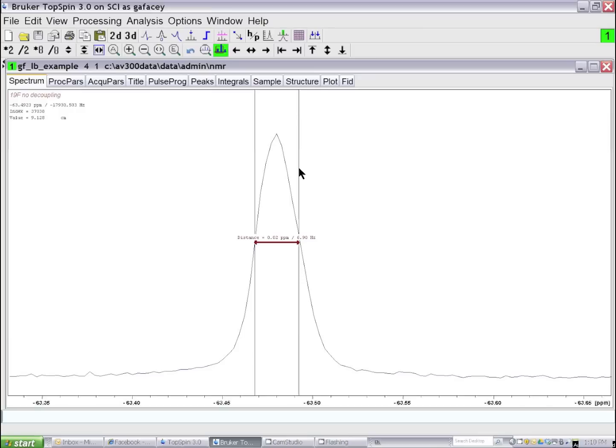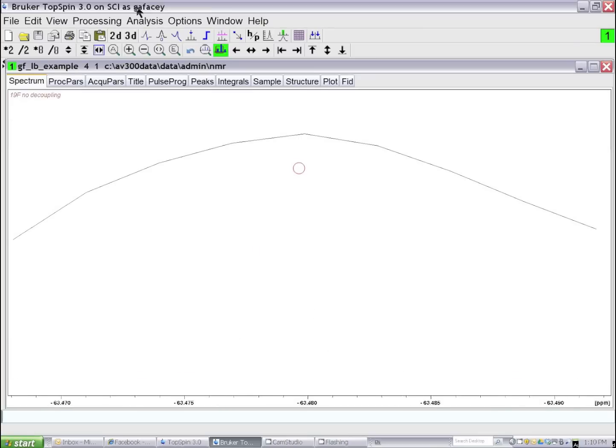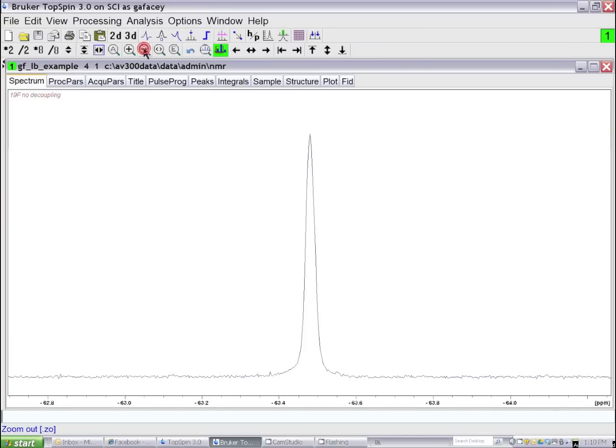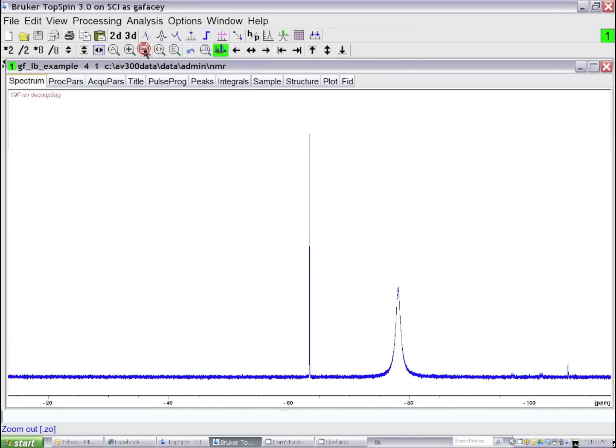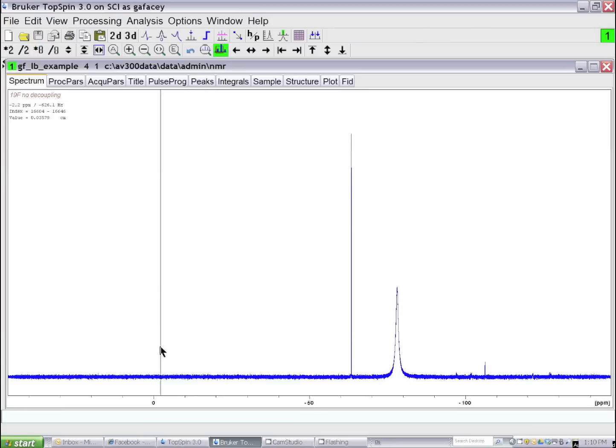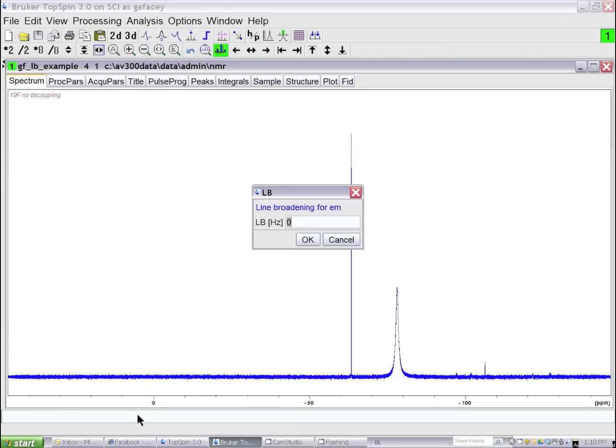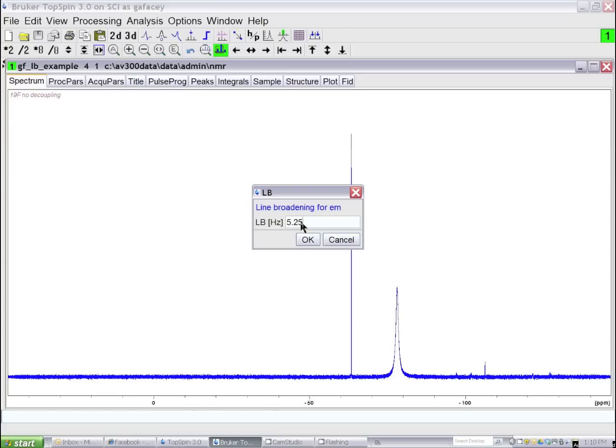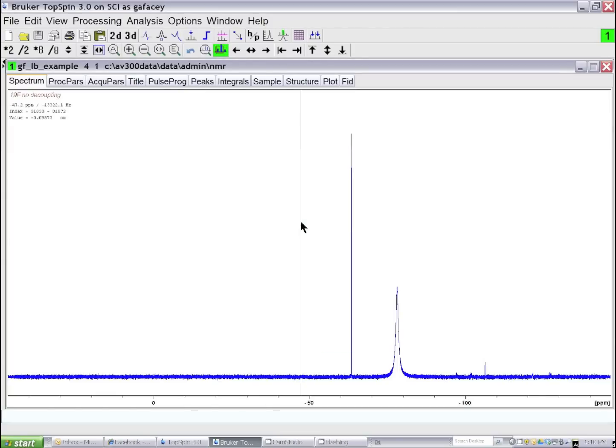The most intelligent way to set the line broadening parameter is to use about three-quarters of the line width of the sharpest line of interest.